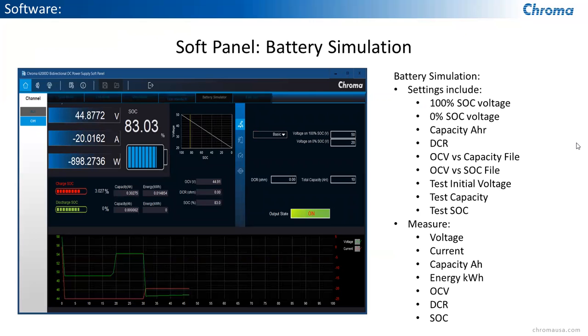This is because not all batteries charge and discharge linearly. There are various load discharge and charge profiles for different battery types, whether it's lithium or lead acid or any other type of battery. We have the ability to import that data through an Excel or CSV file to create that actual curve, and our unit will operate based on your discharge curve and your charge curve for that particular battery that you want to simulate. We can do measurements for voltage, current, ampere hour, energy and kilowatt hours, open circuit voltage, DC resistance, and state of charge as well.